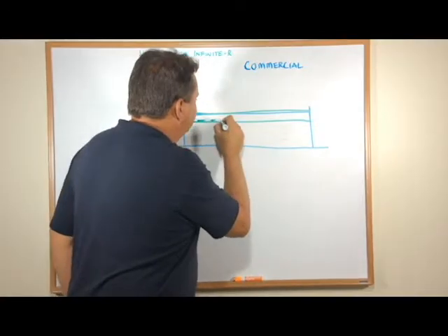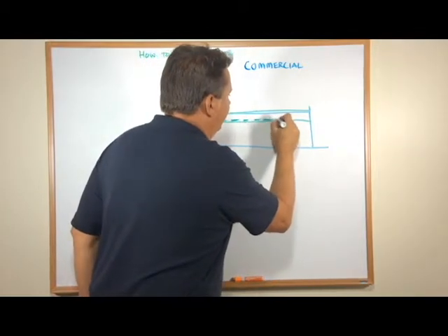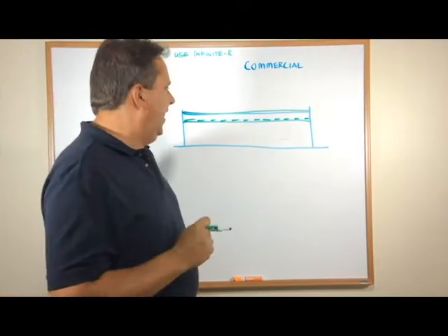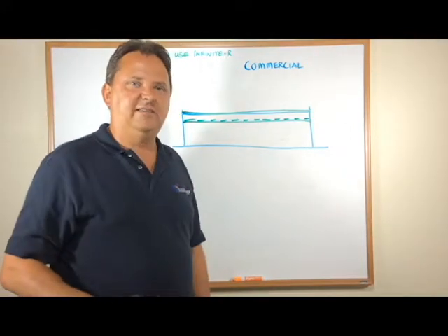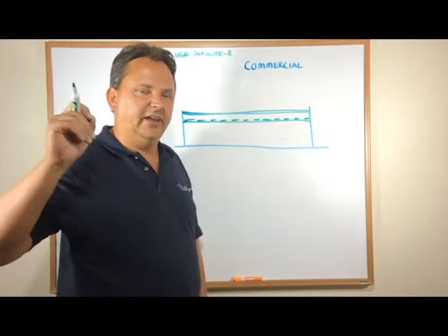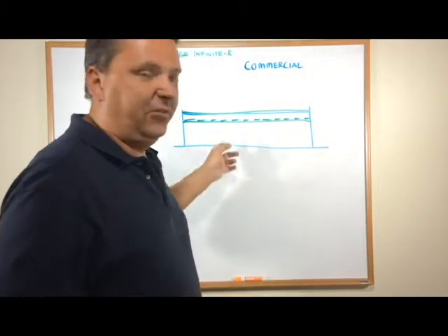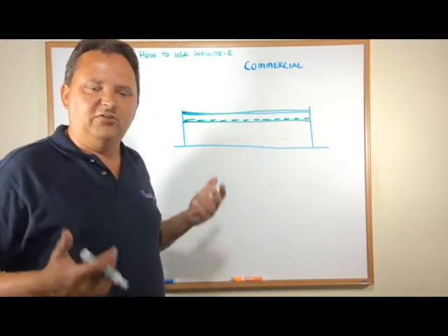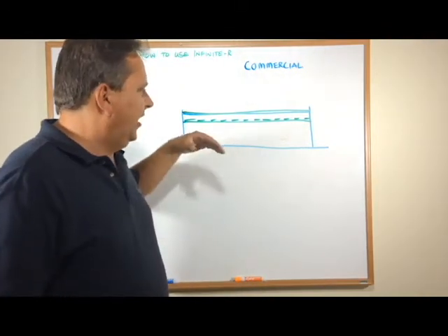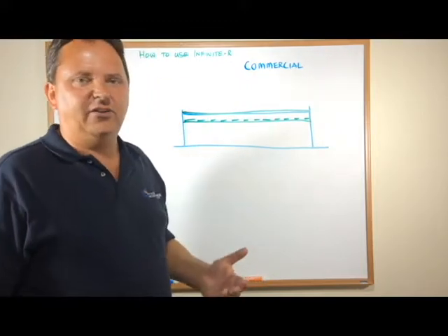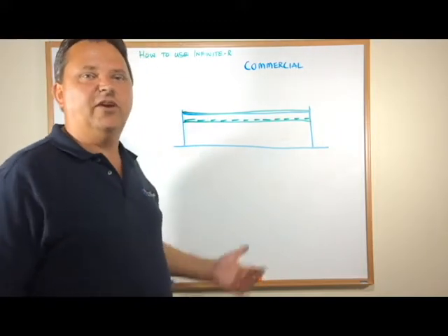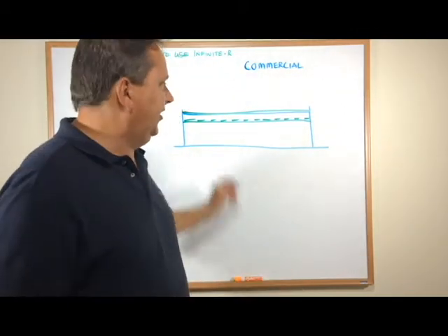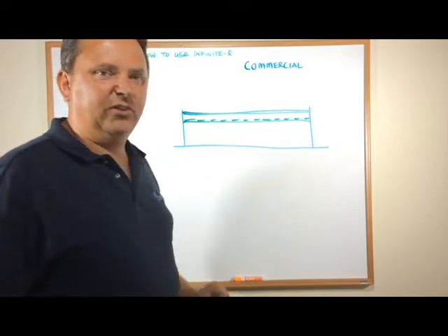By doing this, we actually create a thermal layer within the ceiling itself, thus dropping the temperature of the roof and thus reducing the amount of heat that's being transferred from the ceiling into the building. It does another thing also. It allows for the excess heat inside the building to be absorbed and conserved for later, or helps reduce the peak demand of the air conditioner and allow the air conditioner to remove that heat at a point in time when it's not as loaded down, and therefore giving energy savings. So the second option is always to put it above the ceiling tiles.